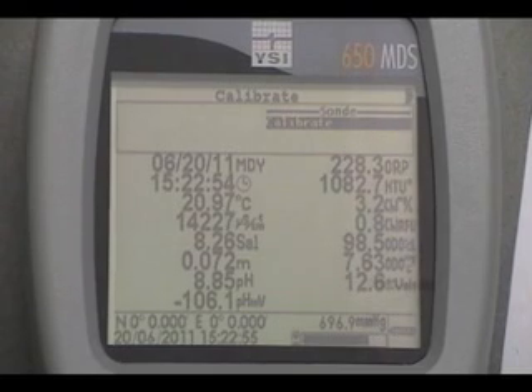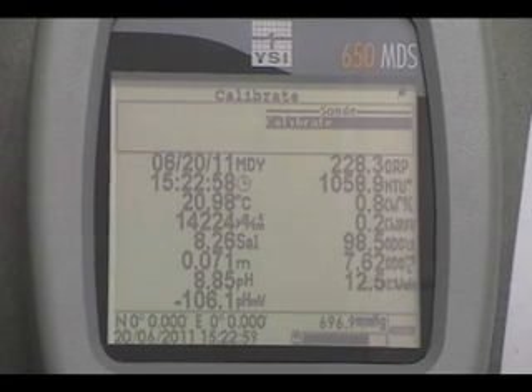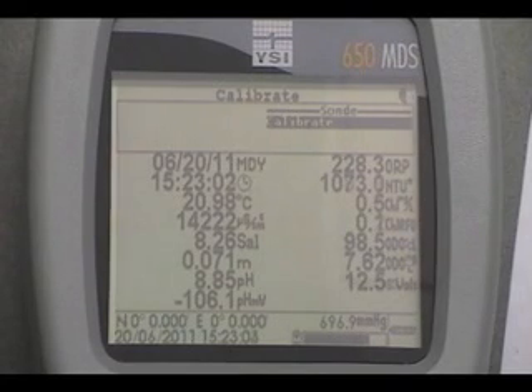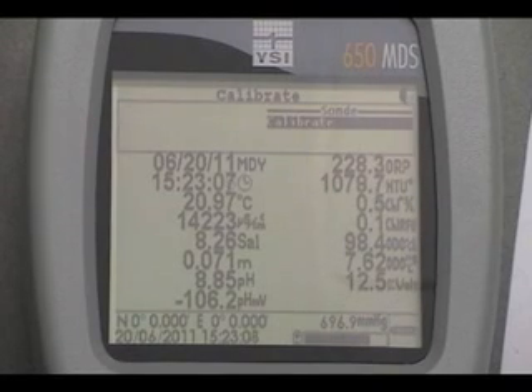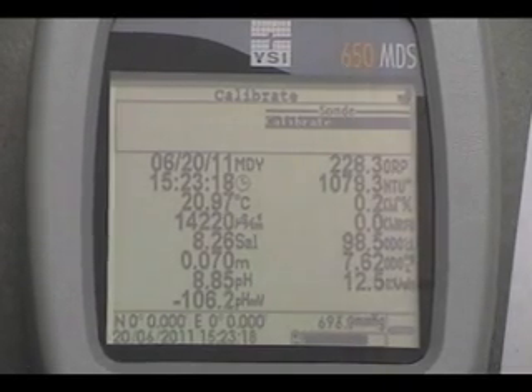Step 7. Monitor the stabilization of the ORP and temperature readings. Once they are stable for approximately 30 seconds, record the pre-calibration ORP value in millivolts on the calibration worksheet. If the probe is functioning within specifications, the ORP reading should be within the range of 221 to 241 millivolts at normal ambient temperature. Step 8.